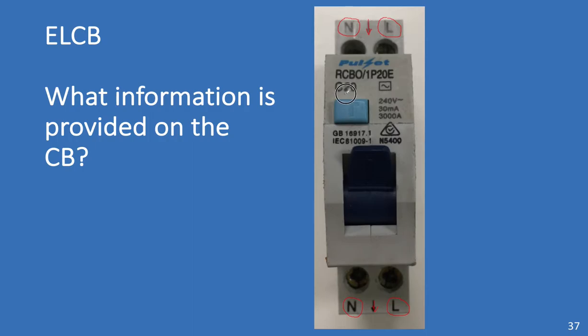It tells us here that it is 20 amps. The C is telling us it's a C curve. Symbol telling us it's AC. The button. You can see the T on the front is the trip test. We know it's 240 volts AC rated. Then we've got this 30 milliamps and 3000 amps. So, what are they about? The 30 milliamps is the trip leakage and the 3000 amps is the fault level. So, this circuit breaker can only handle 3000 amps fault level. The previous one was able to handle 9000 amps fault level.